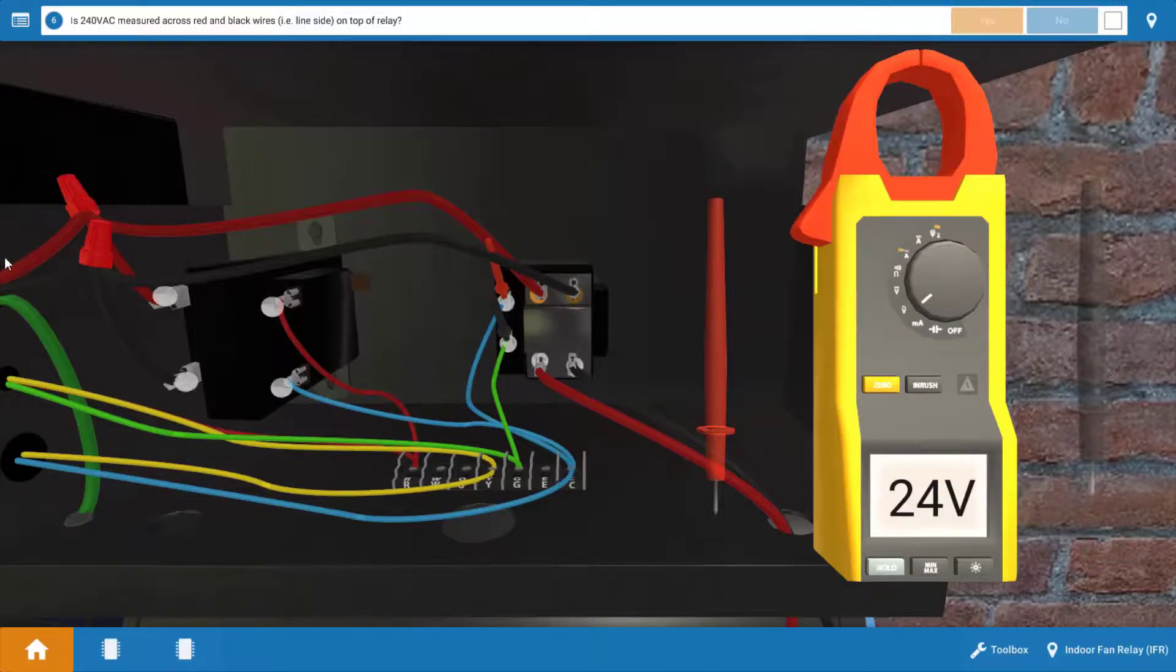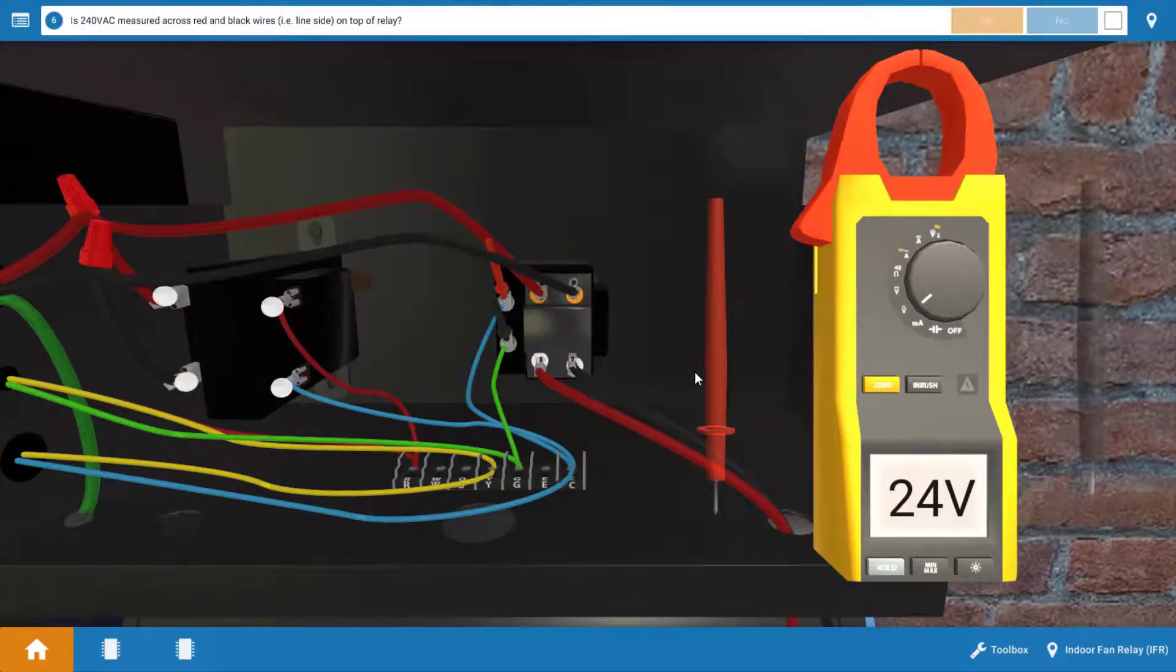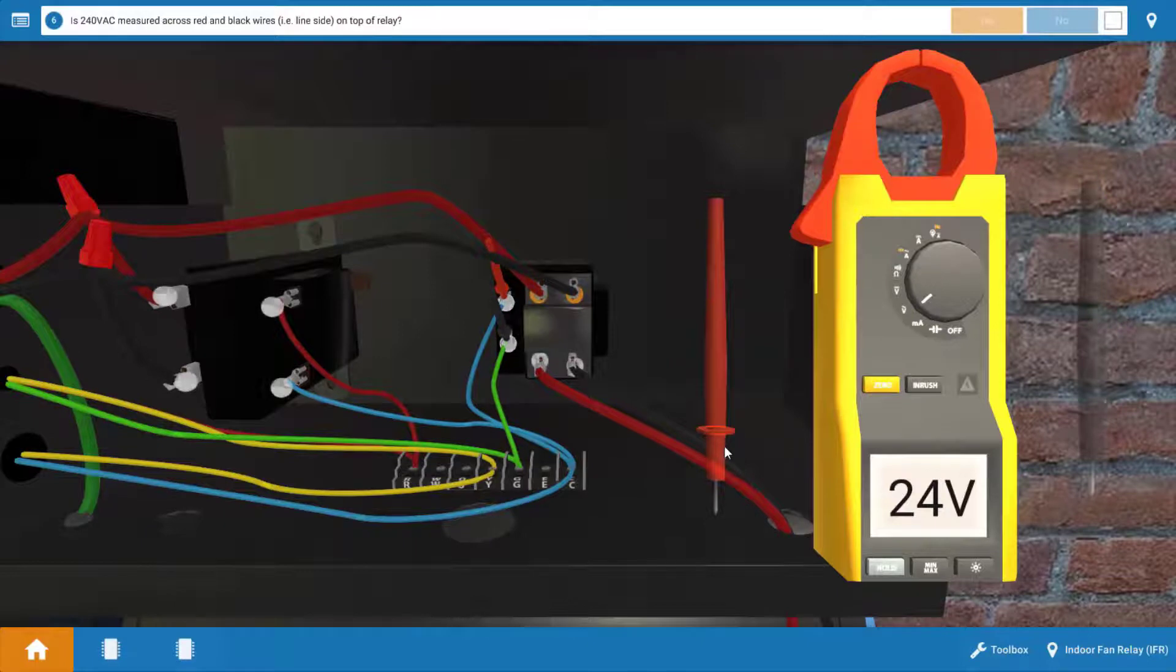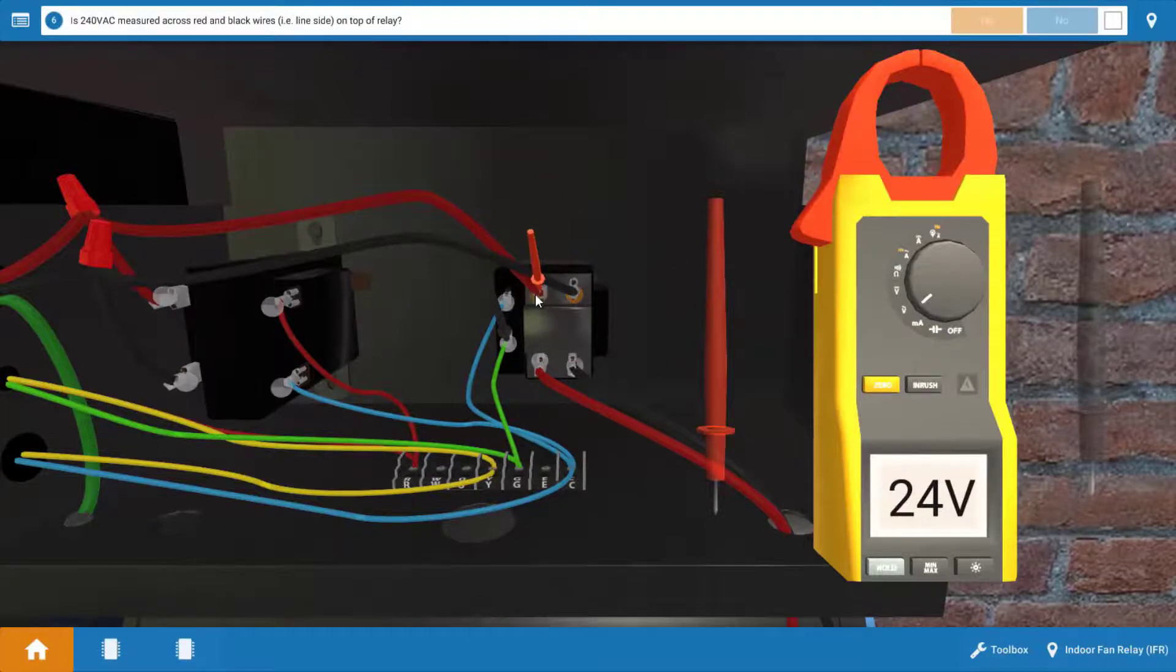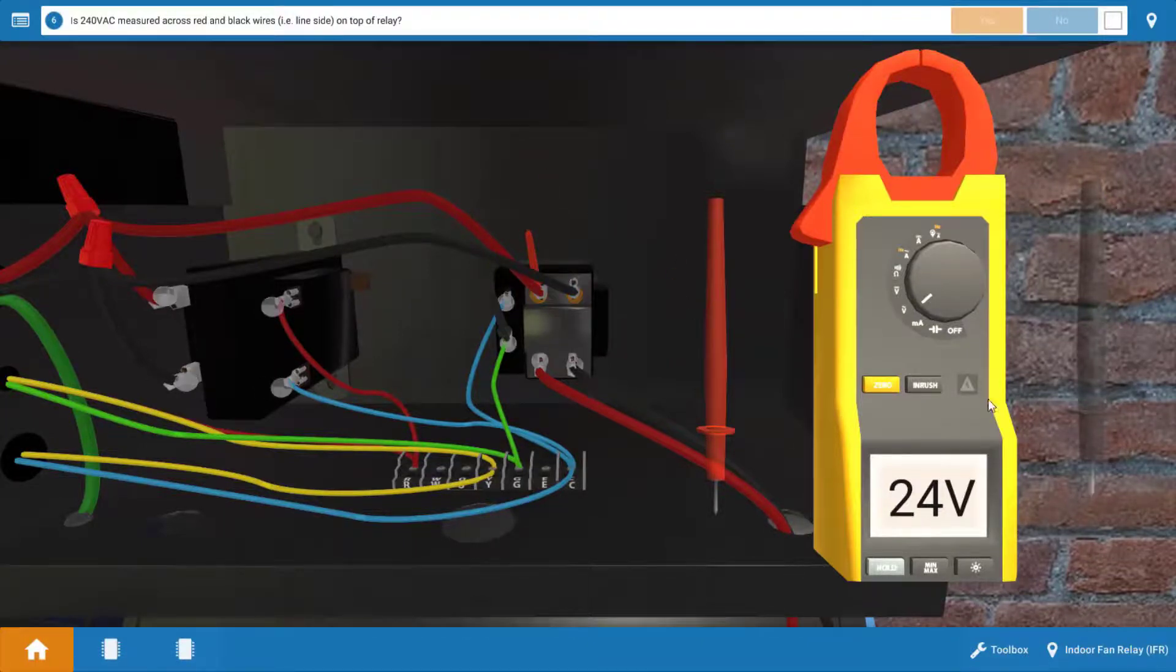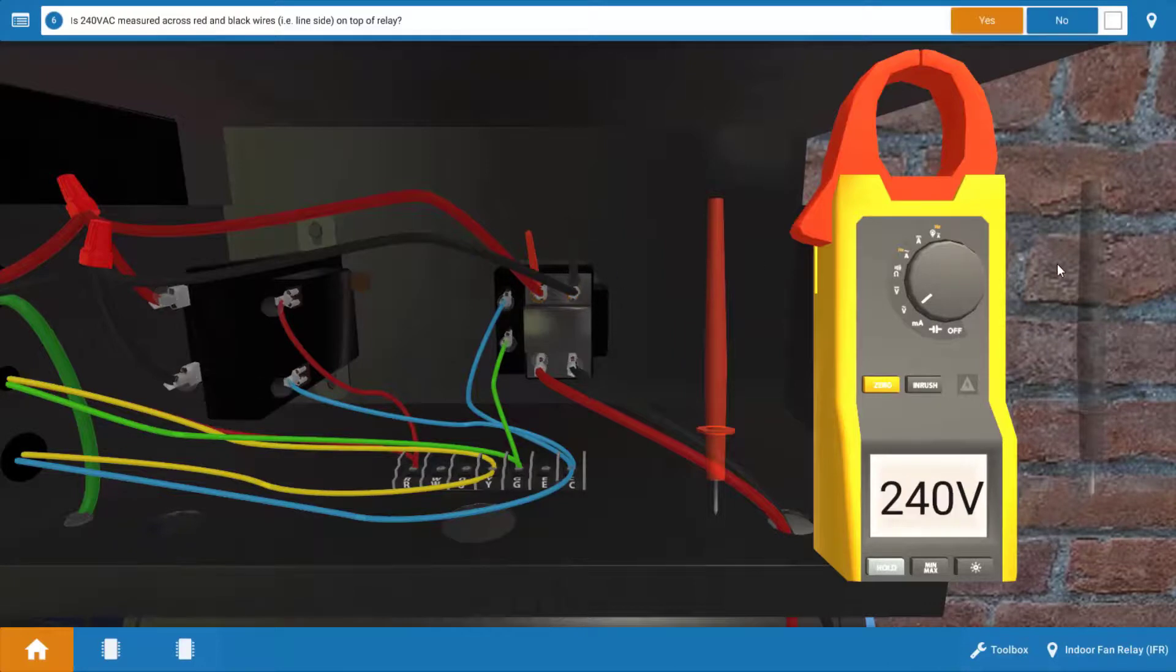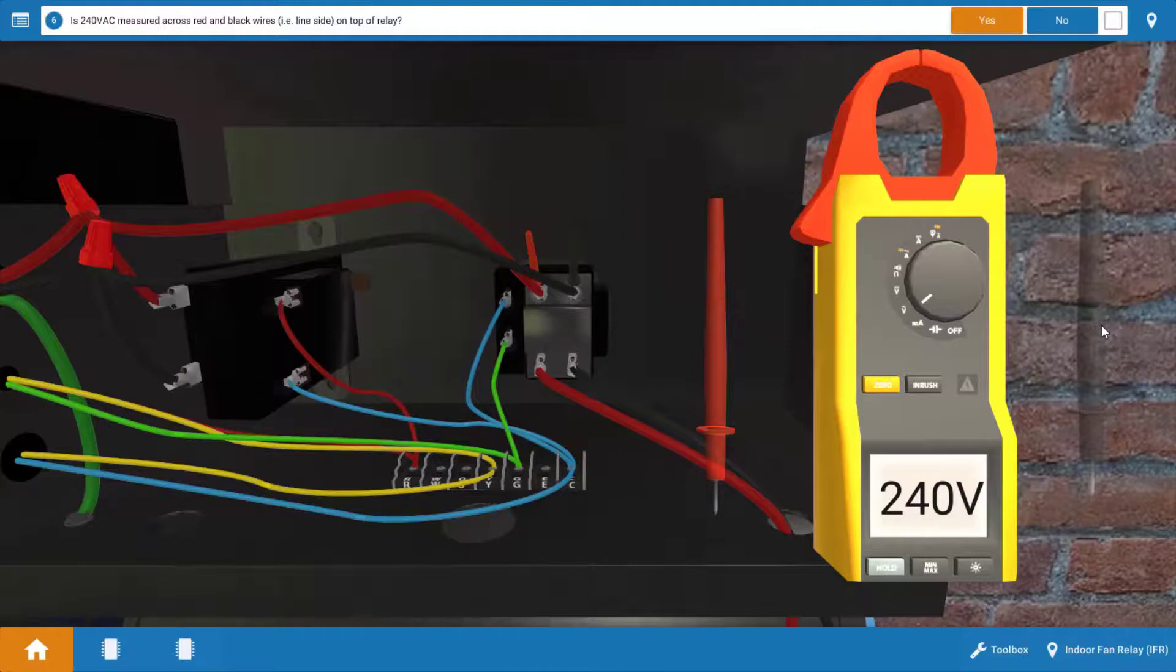Now we could potentially have a break in these wire nuts. So we're going to check that here by dropping the meter leads on those two connection points and verify that 240 is there at the relay. And there we have it, 240 volts. So we've got power to the coil. We've got line voltage coming in.